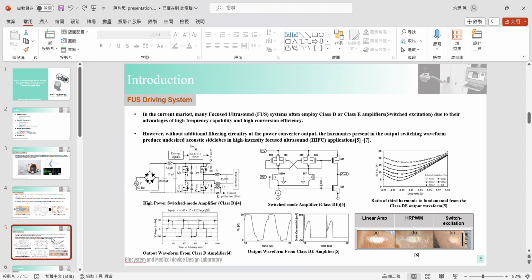However, these amplifiers have limitations in focused ultrasound applications. Switched excitation amplifiers rely on PWM modulation of the input signal, resulting in output signals composed of numerous square waves. This causes higher order harmonics in the output signal, leading to side lobes in the acoustic field, which in turn affect the energy and position of the therapy.